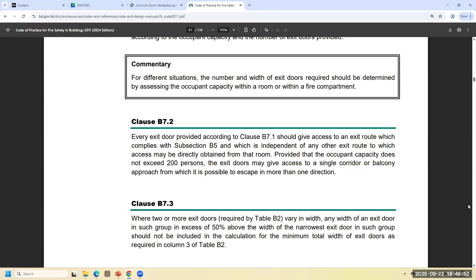After that, you need to identify the number of exits and their width. Remember Table B2, which we mentioned in the last lecture, on page 34 of the Code of Practice booklet: 4 to 30 occupants requires one exit, 31 up to 200 requires a minimum of two exit doors and exit routes, and the width is identified accordingly.